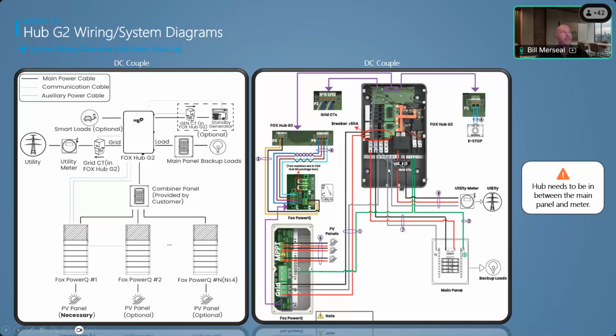We also have the way the CTs are supposed to go inside the hub as well. So whether you put a 200 amp breaker right in here, or do it directly, it will show you exactly how those CTs go, what direction the arrow is, what L1 and L2 are - we even color coded the L1, L2 wiring on the CTs to make sure you know which one is which, so when you wire into the hub, you know exactly where it goes. That's something we try to make as easy as possible for you guys.